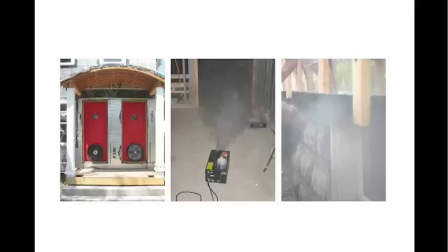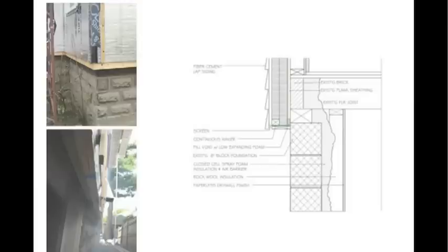The big leakage area was the sill. At the sill we have this exterior insulation which comes down and then it stops. And then the interior insulation in the basement picks up. So you've got this hiatus. We do a blower door test. The blower door pressurizes the house. We fill the basement with theatrical fog. And we find out where the leaks are. That's how we were able to get down to 590.